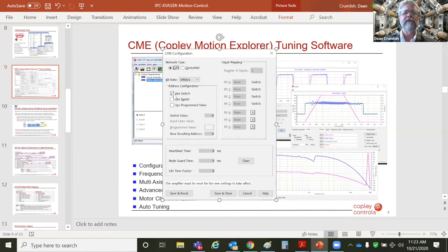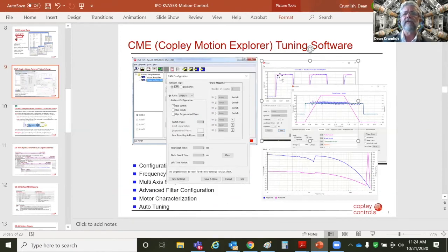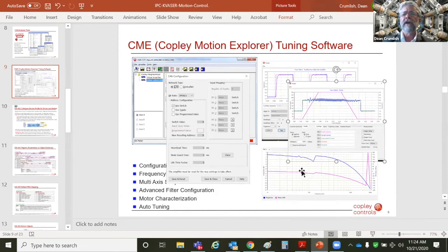And this is using a switch, so you can turn the switch on the drive to get the node address. You don't have to use the switch. You can program the value to whatever node you want that node to be. But this is the basic idea of the CME setup and tuning software. You can tune the current loop, make some moves, do some frequency, and you can prove out the mechanical system. And then you put it in a CAN mode and hand it over to the software engineer and say, all right, I've set up everything, I've done homing, you go ahead and program it.